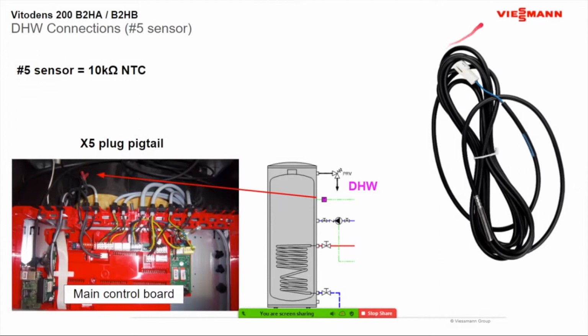So as you can see over here, there's a number 5 on the plug itself on your sensor, as well as when you look on these 2 little red tabs on the boilers, it will say number 5 as well. And you're just going to plug that in, and remember it's auto recognized. So as soon as you plug it in, it now knows you have domestic hooked to the boiler.